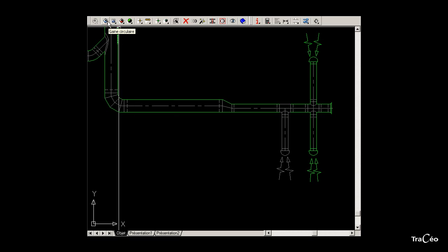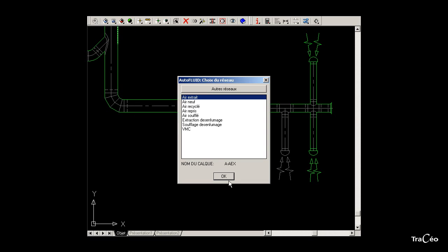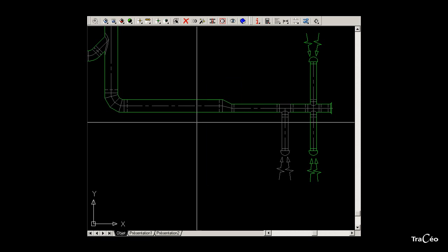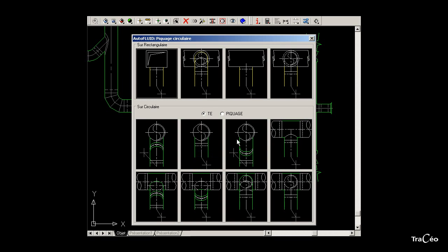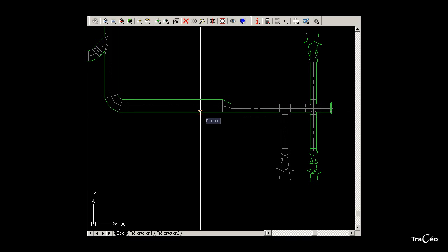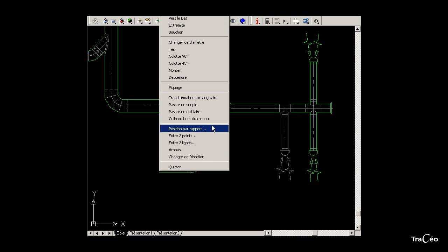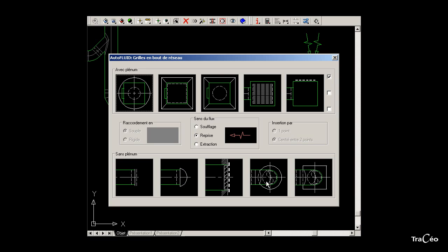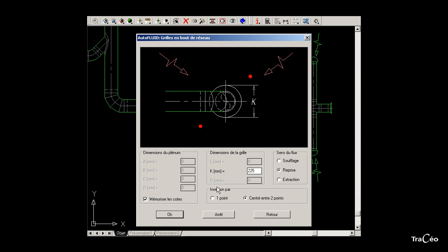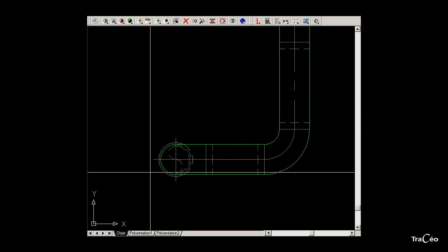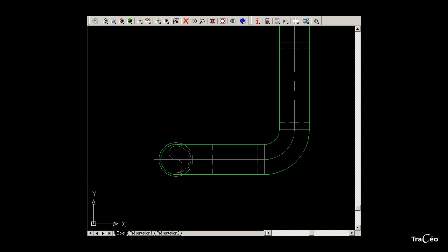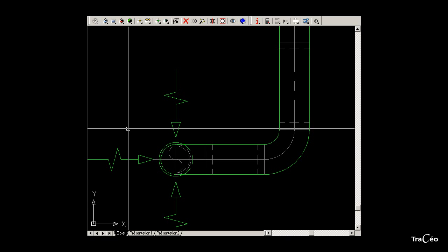For one last branch, select the circular drawing command, then select the type of network and the profile size. Right-click to select the connection option. This time choose a tapping connection with a connection from above at 45 degrees. Select the duct to connect to, then click to specify a second and third point. Right-click and select register at the end of network. Choose the direction of flow and the type of register. Insert the dimension of the register and dimension K, then click OK. Now position the arrows — click on the first point and place the arrows. Confirm and the command is complete.